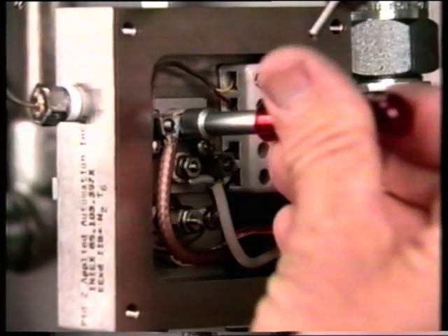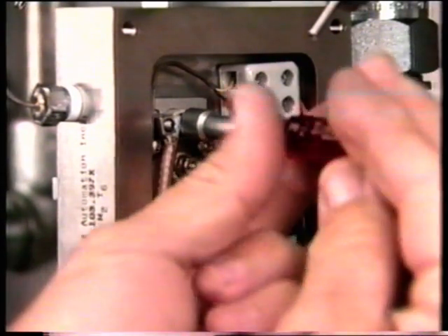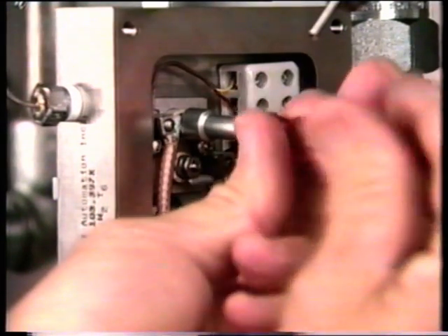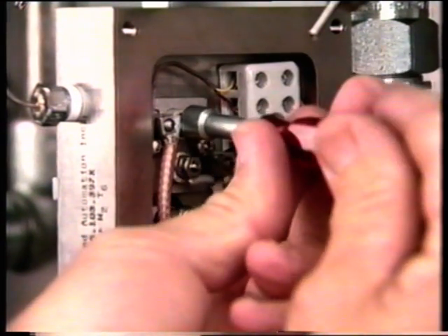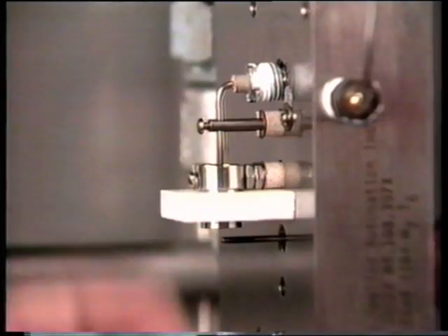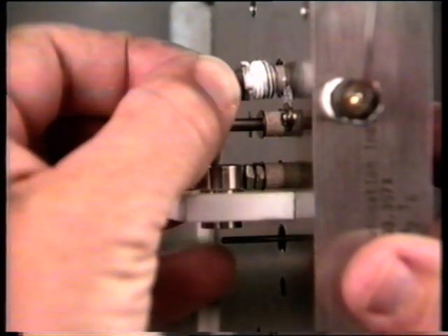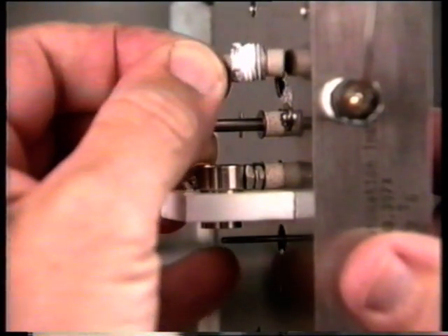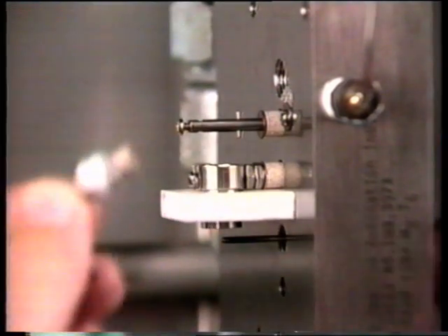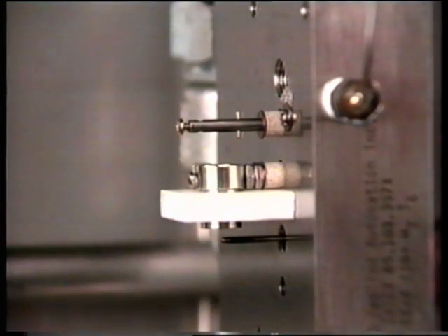Remove the coax center conductor of the bias ignite cable from the bias ignite electrode. Remove all the nuts and washers from the electrode. Pull out the bias ignite electrode and burner tip far enough to clear the burner tip ferrule and lift the burner tip from the hole in the bias ignite electrode. Don't remove the bias ignite electrode.